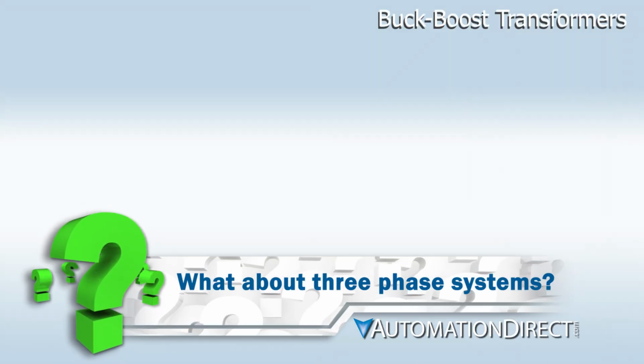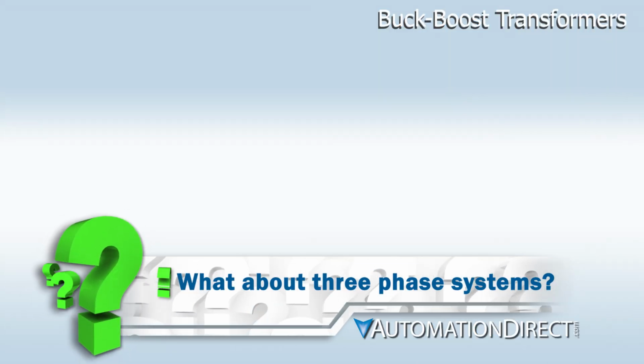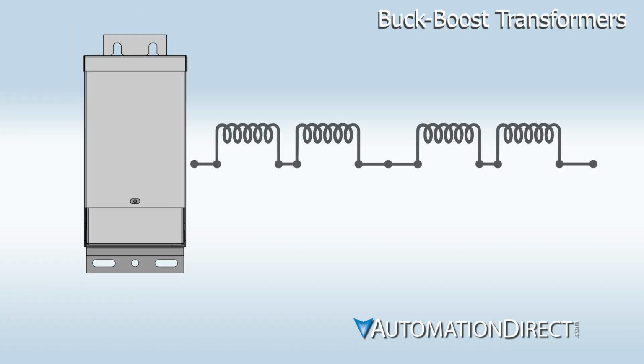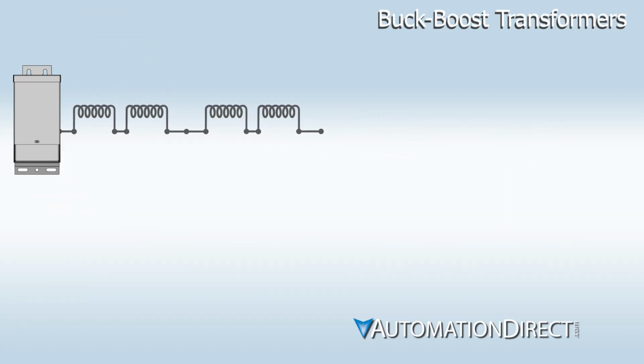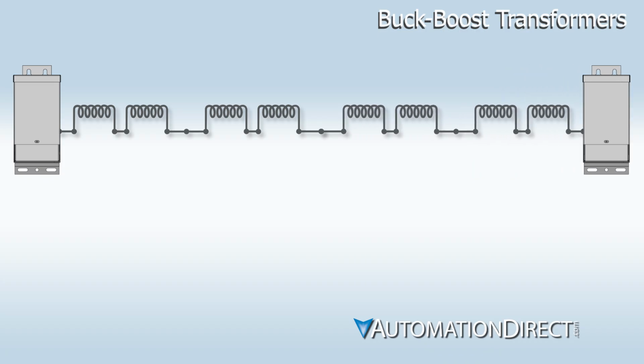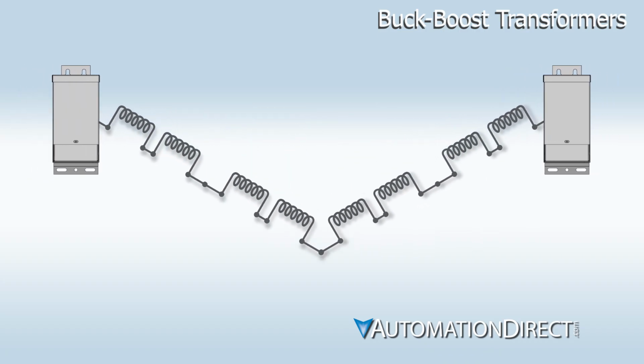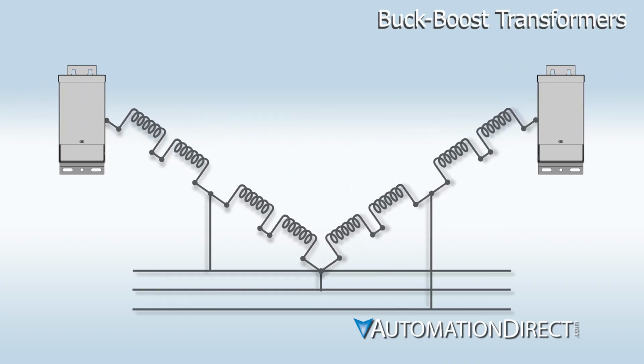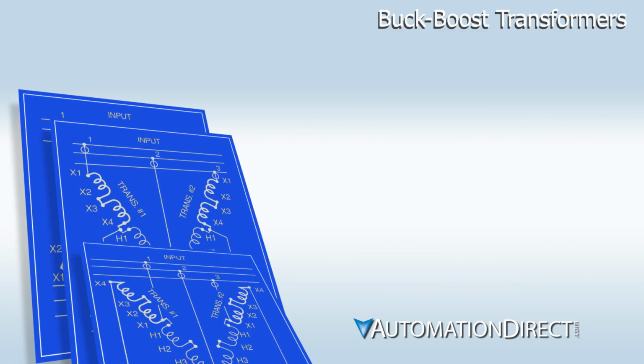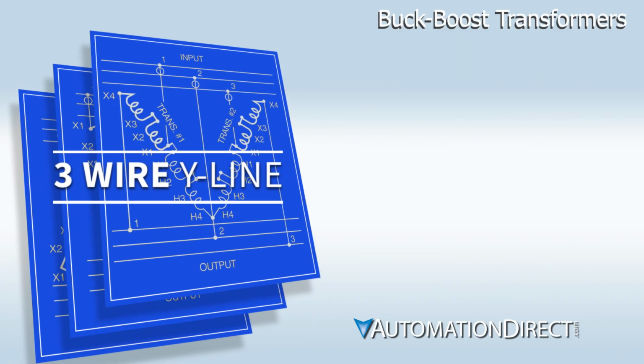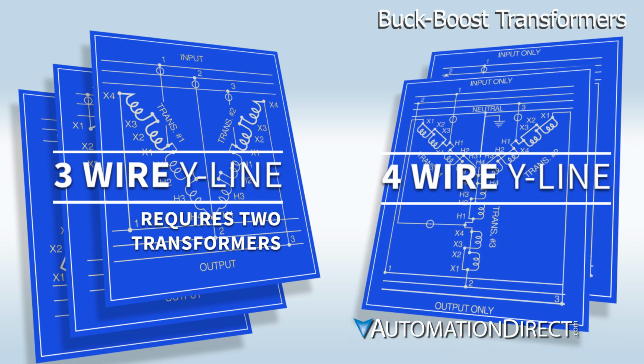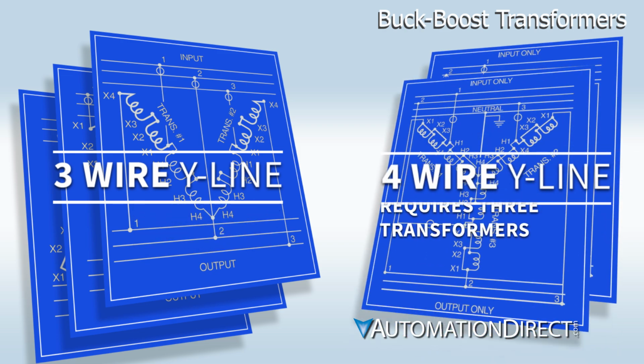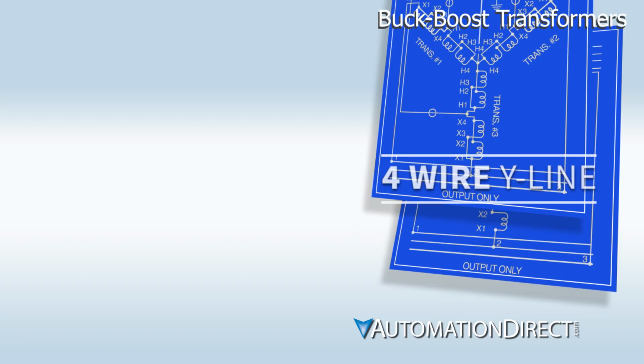Can you use buck-boost transformers in a 3-phase system? Yes. While buck-boost transformers are single-phase transformers, multiple units can be used to buck or boost 3-phase voltage installations. The number of units to be used depends on the number of wires in the supply line. For 3-wire Y supply lines, 2 transformers are needed. For 4-wire Y lines, you would need 3 transformers.